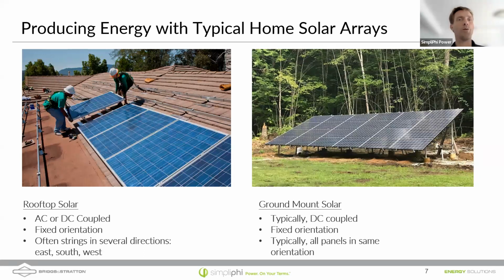Let's look at the typical energy production with home solar arrays. Probably the most common is rooftop solar. This could be AC coupled or DC coupled. An AC coupled system would have microinverters on it, and you're sending that AC voltage down off the roof to your load center. These are almost always fixed orientation, but sometimes there will be several strings with different directions. You might have an array pointing east, south, west, or if you're in the southern hemisphere, north. The idea is typically that you're matching the shapes of the roof that you're installing on, and I'm getting ready to put one on the south face of my roof as well.